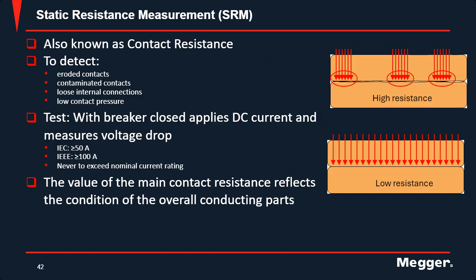One point I want to add to this: international and national standards set forth a guideline for the static resistance measurement, or contact resistance, to eliminate any risk of attaining crazy high values for your results because your test current is too low. Standards like IEC 56 state that the resistance is to be measured using a minimum of 50 amps, and not to exceed the breaker's nominal current.